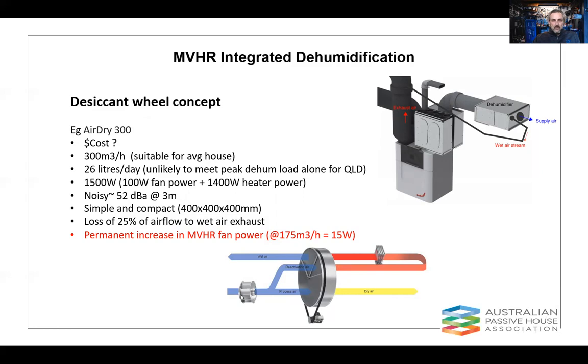And in this one, it actually has a bit of a loop. Essentially what's done is a heater is used to raise the temperature of that portion, that air flowing through that portion of the wheel. And essentially what that does is evaporates the moisture off the desiccant crystals, and it can be then discharged. So the cooler air comes, those desiccant crystals absorb the moisture for, let's say, 300 degrees of that circle, and in the other 60 degrees we reheat that air, get it up so we re-evaporate the moisture, and then we dump it.